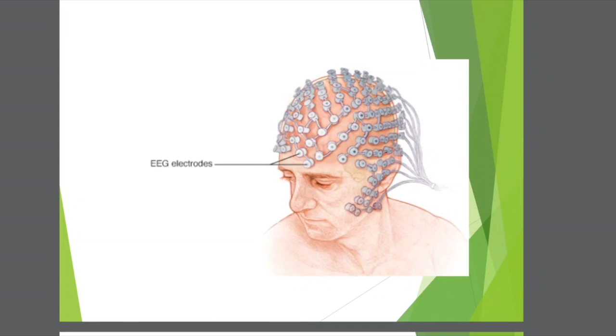The main blocks of electroencephalograph are electrode montage selector switch, amplifier and filters, analog to digital converter, then EEG representation on computer monitor, chart drive and writer unit, EEG representation on chart. And montage selector. Montages are patterns of connection between the electrodes and the recording channel. The montage selection switch is used for selecting a particular channel. Different channels convey different information.